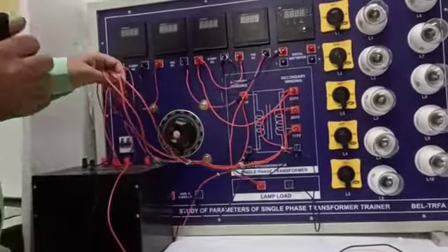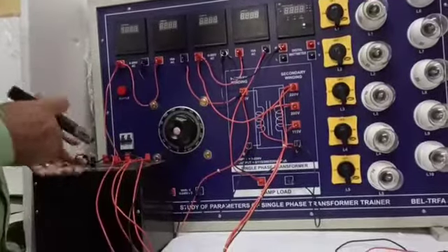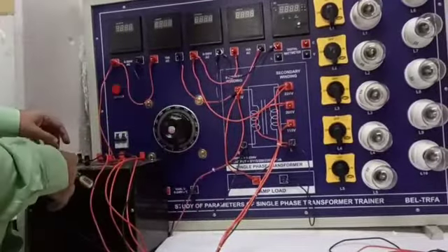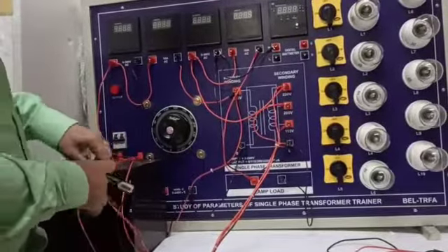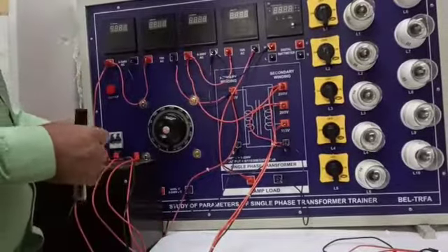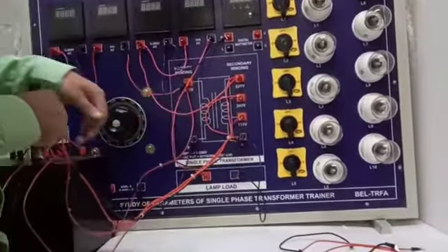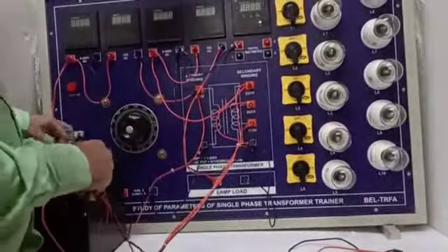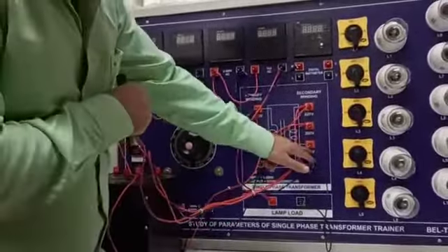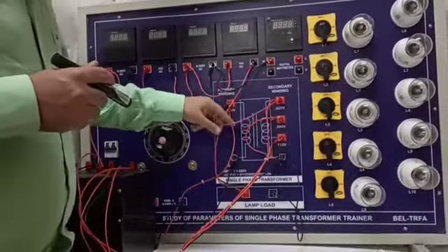So first, how to make sure that we have made the right connection? The neutral of primary voltage should be connected at 0V on the single-phase transformer. The 220V output should be connected to the primary winding 220V. Similarly, the neutral of the secondary winding should be connected at 0V secondary winding. 115V should be matched to 115V from the transformer to the panel. Similarly, 200V and 220V.